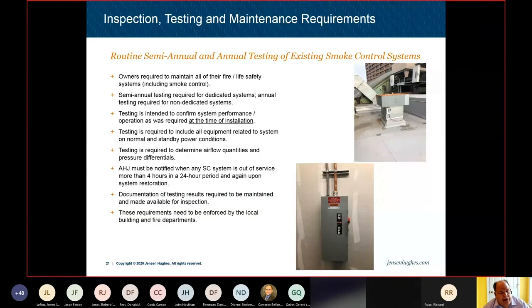So as an example, if you have below grade spaces that go beyond 60 feet and you have a smoke control system as part of that, normally that's done with normal HVAC equipment that's also doing the normal supply and returns for that. In those, since they're used more often, if they tend to break, someone's going to complain because it's too hot or too cold in the building. So that's the difference why a smoke control test for non-dedicated systems is annual, because they're basically exercised on a daily or weekly basis, and they get fixed much more readily, as opposed to the stair pressurization system that's just sitting there. It's never really being utilized except during the emergency condition or during testing of the inspection, testing, and maintenance.